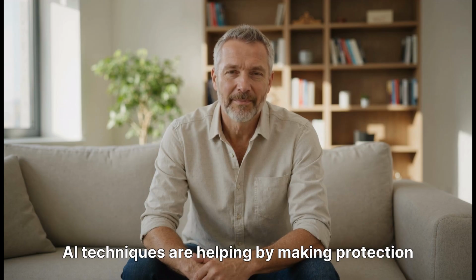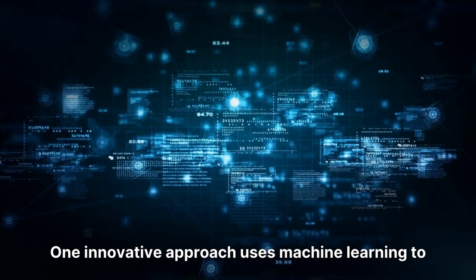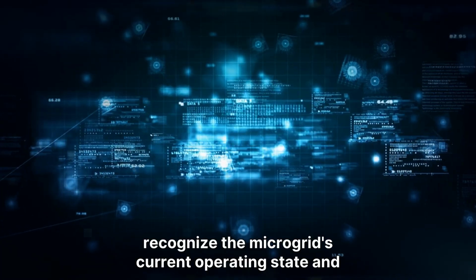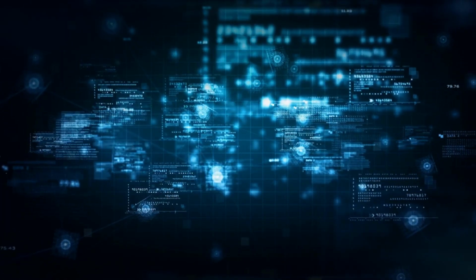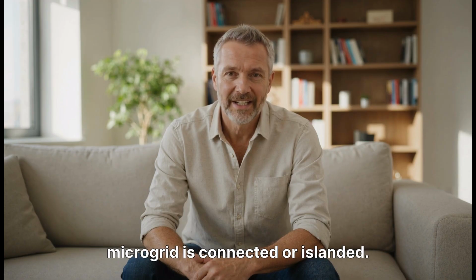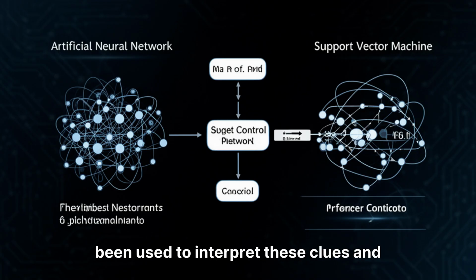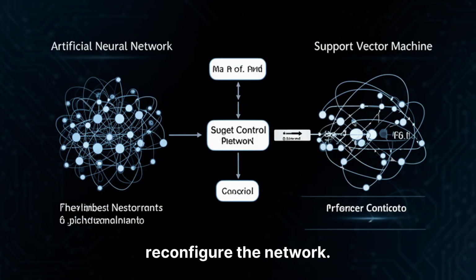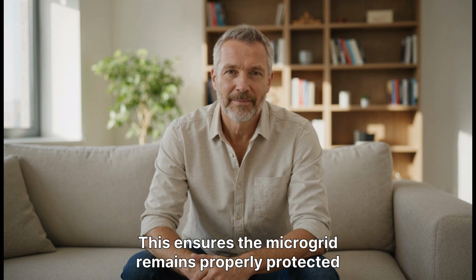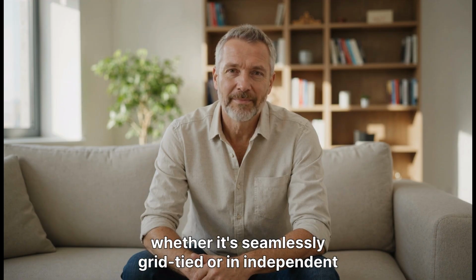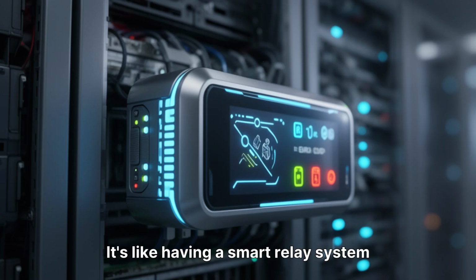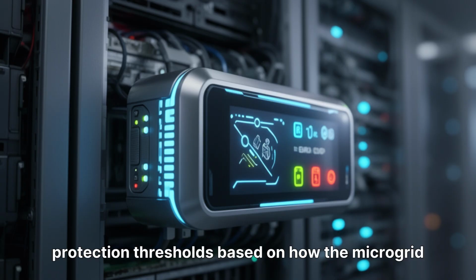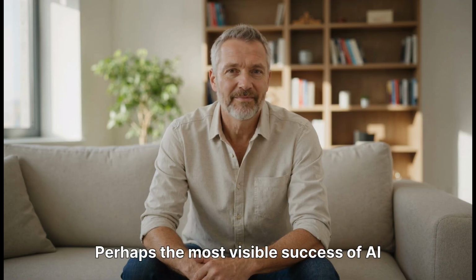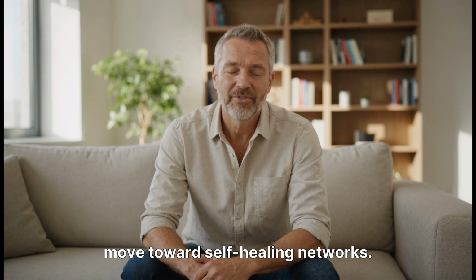A protection setting that works when the microgrid is grid-connected might not work when it's islanded with only local generation. AI techniques are helping by making protection schemes adaptive. One innovative approach uses machine learning to recognize the microgrid's current operating state and adjust protection settings on the fly. For instance, it might analyze electrical measurements and their correlations to determine if the microgrid is connected or islanded. A hybrid model, combining an artificial neural network and a support vector machine, has been used to interpret these clues and reconfigure the network. This ensures the microgrid remains properly protected, whether it's seamlessly grid-tied or in independent island mode. It's like having a smart relay system that knows when to tighten or loosen protection thresholds based on how the microgrid is operating.